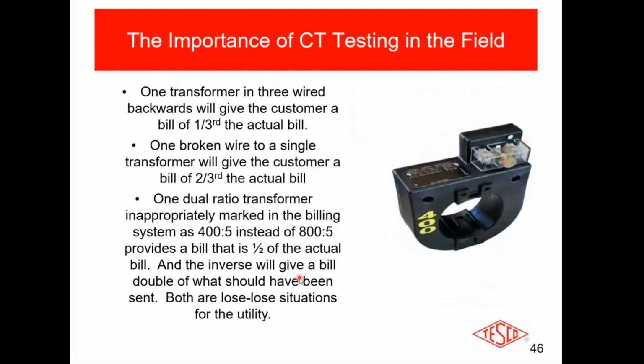Why is this important? Well, it's important because if I got just one transformer wired backwards, remember that little white dot there? It tells me which way is front. If I got a transformer wired backwards, it actually is canceling out the next transformer. If it's a perfectly balanced load, and typically they're roughly balanced, I'm actually only going to give that customer 1/3 of what he's actually using. 1/3 if I got a transformer wired backwards.